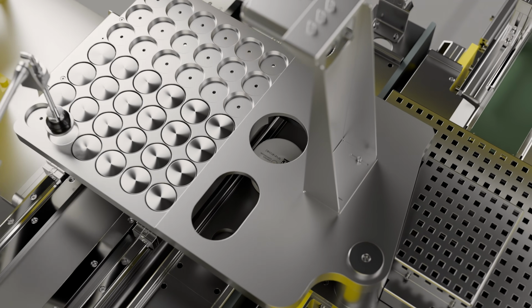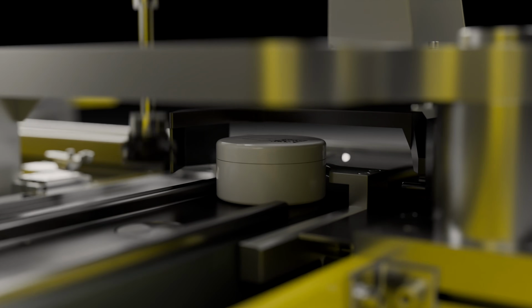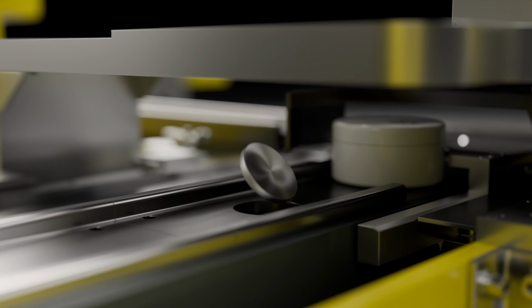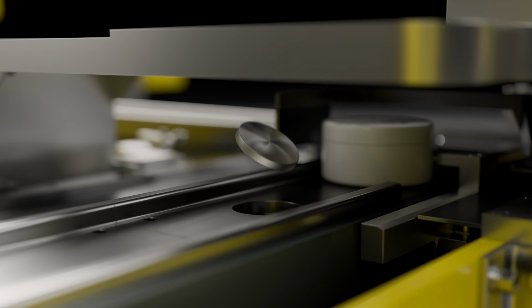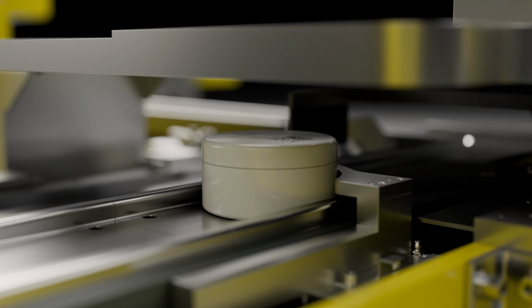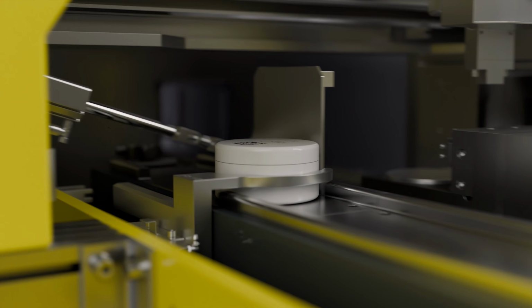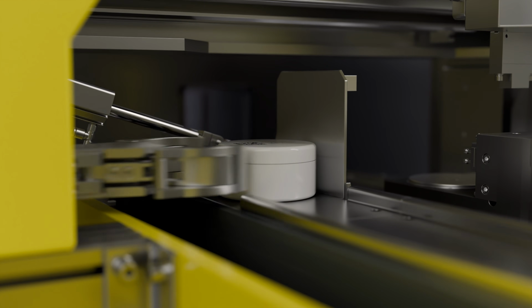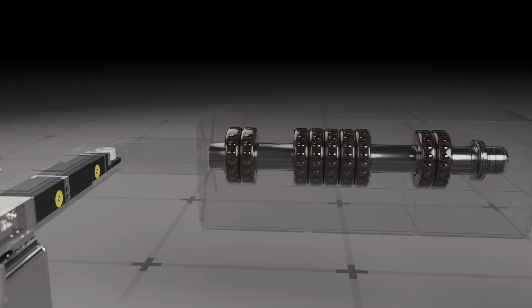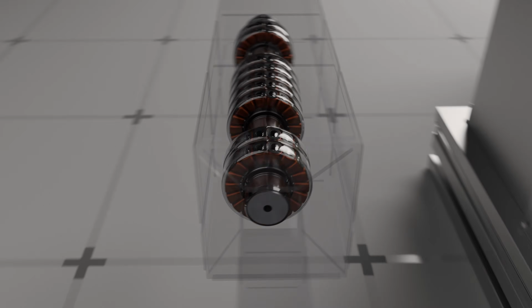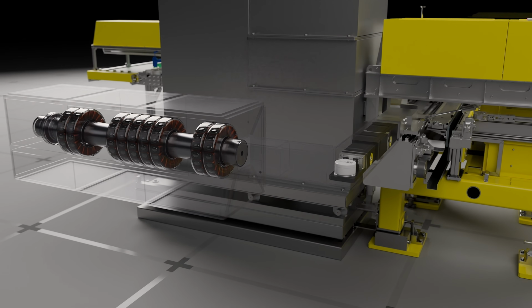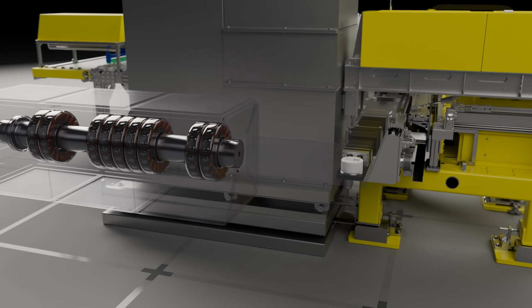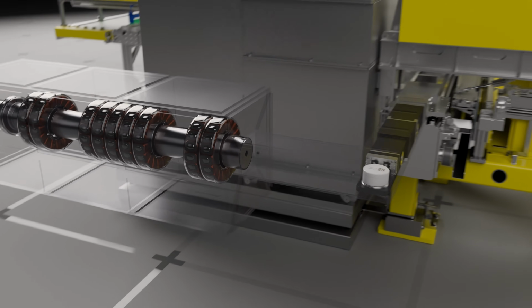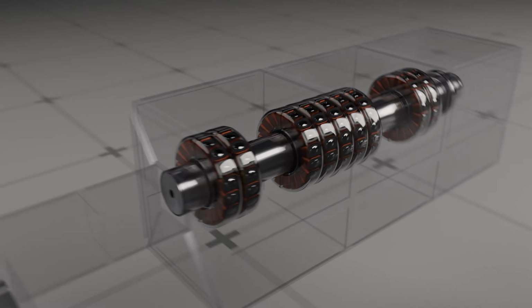At the entry point, each sample is automatically paired with a precision reference disk that acts as a calibration standard, ensuring consistent and precise analytical performance time after time. Together, the jar and reference disk are carried towards the activation chamber, the heart of a PhotonAssay unit. Once it arrives, a heavy plug seals it in place. From this moment on, everything is fully enclosed, interlocked, and monitored. If any door or seal isn't verified, the electronic X-ray source that activates the sample simply can't operate.